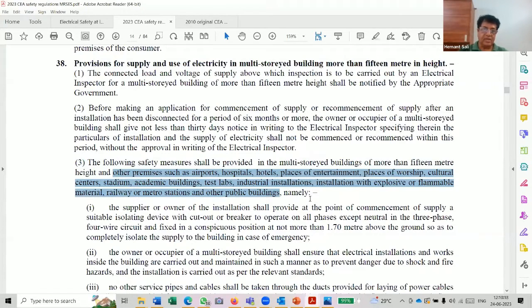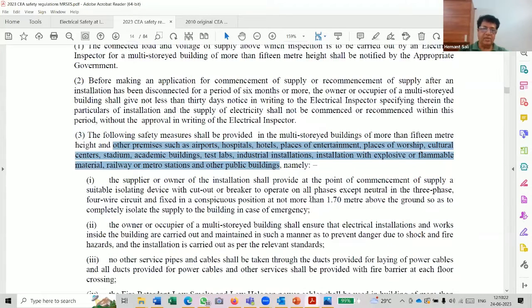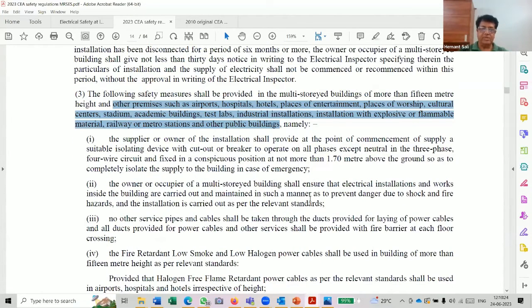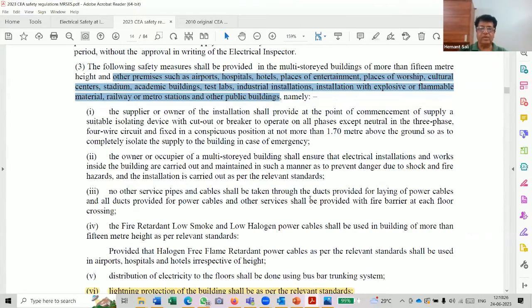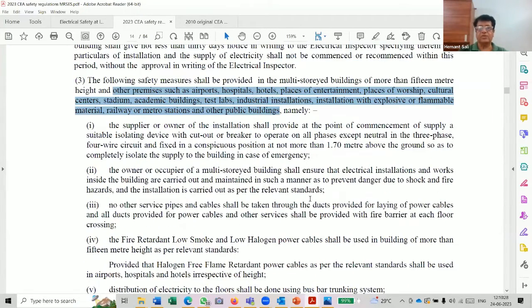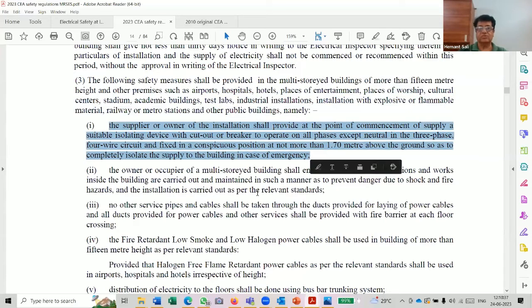Yeah, actually the heading of regulation number 38 should be changed. It should be multi-story buildings and high-risk buildings. That should have been the proper wording, because under this, they mention that other buildings are also included. So that is somewhat confusing, like airports and hospitals, where height doesn't come into the picture. Regarding that, there are a few additions in this regulation. I would like to mention one point where they mentioned there should be a switch for the building to completely isolate the supply of the building. That is interpreted wrongly, because emergency services always have to bypass this switch.